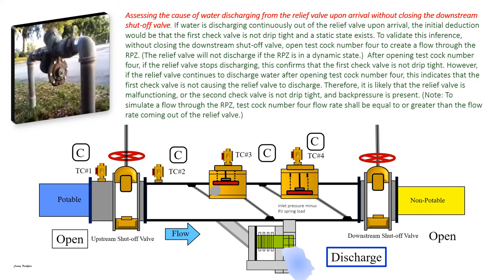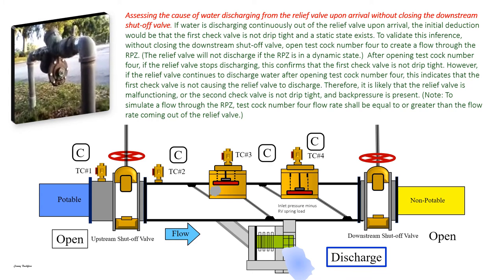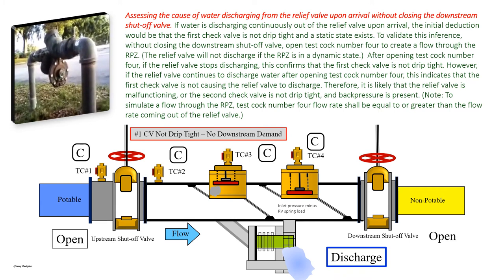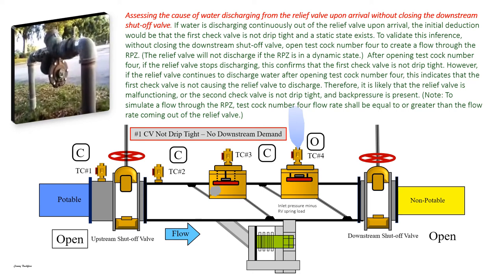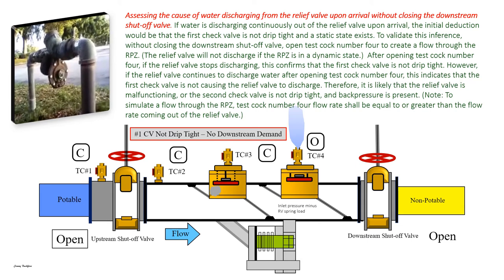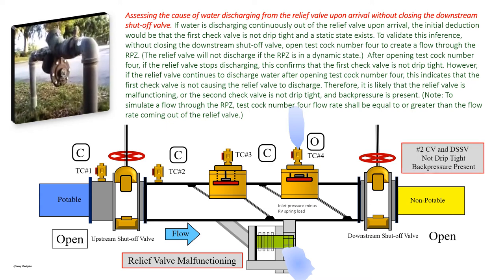Assessing the cause of water discharging from the relief valve upon arrival without closing the downstream shutoff valve. If water is discharging continuously out of the relief valve upon arrival, the initial deduction would be that the first check valve is not drip tight and a static state exists. To validate this inference without closing the downstream shutoff valve, open test cock number four to create a flow through the RPZ. The relief valve will not discharge if the RPZ is in a dynamic state. After opening test cock number four, if the relief valve stops discharging, this confirms that the first check valve is not drip tight. However, if the relief valve continues to discharge water after opening test cock number four, this indicates that the first check valve is not causing the relief valve to discharge. Therefore, it is likely that the relief valve is malfunctioning or the second check valve is not drip tight and back pressure is present.